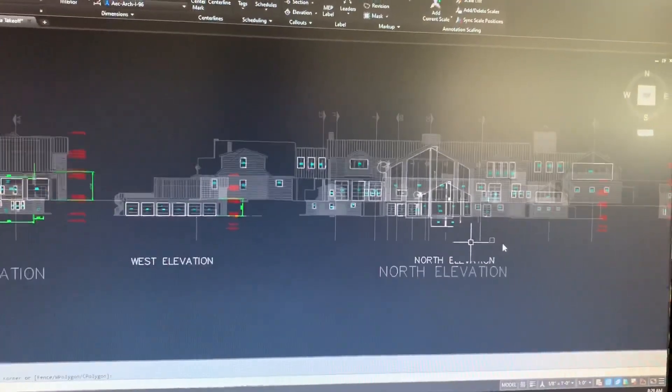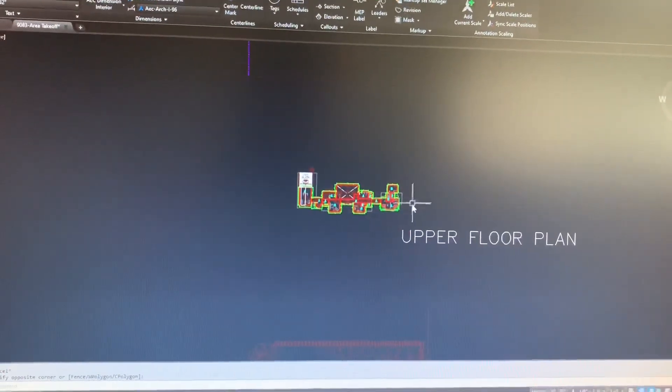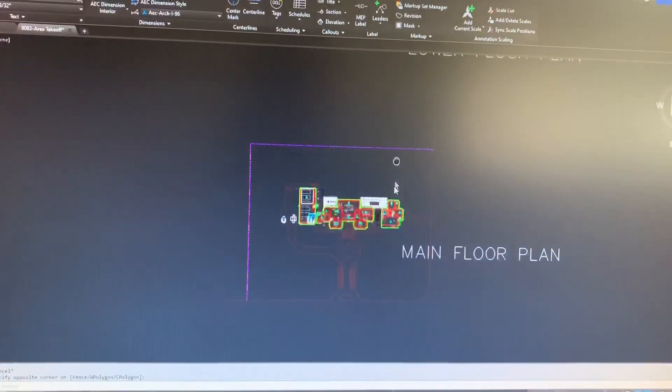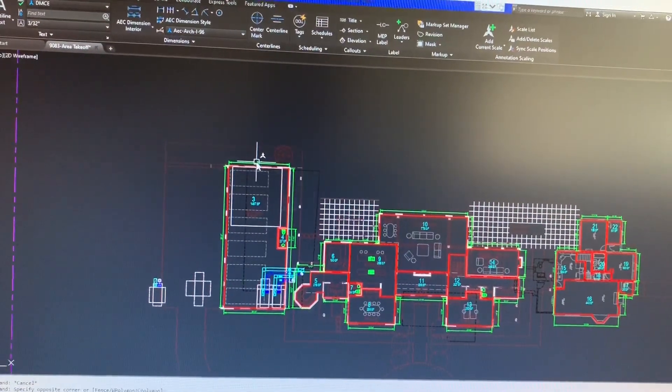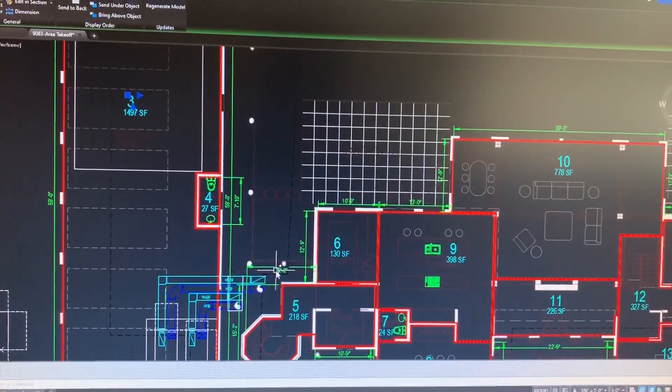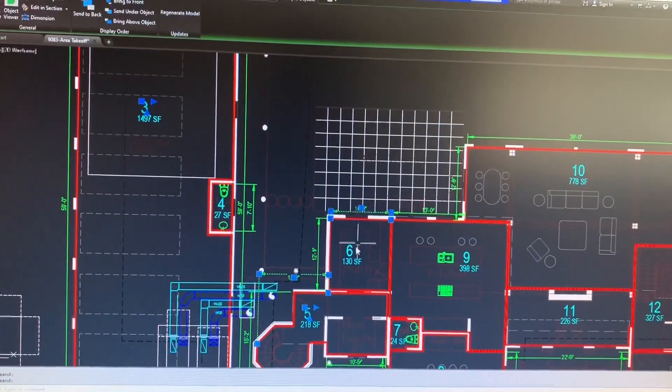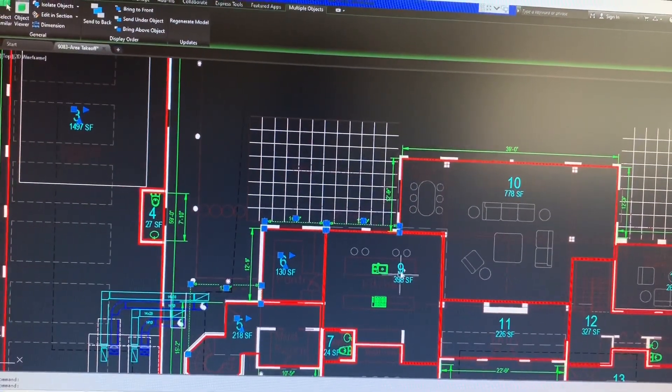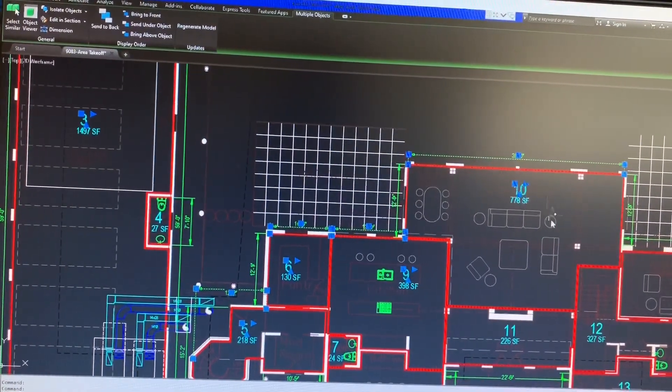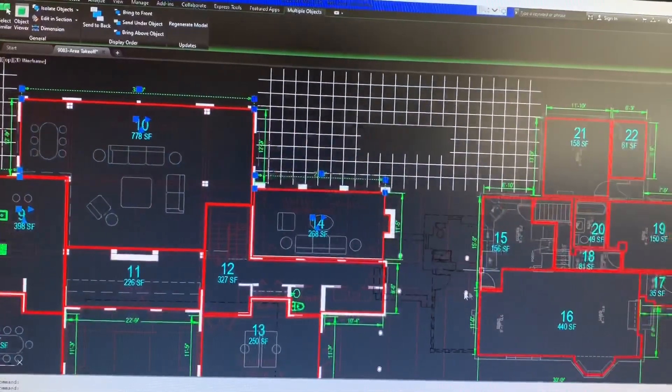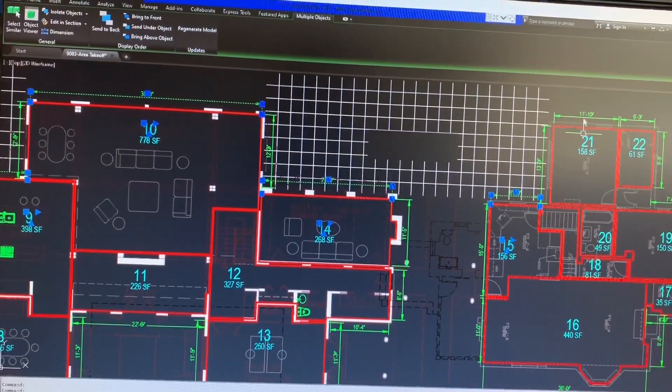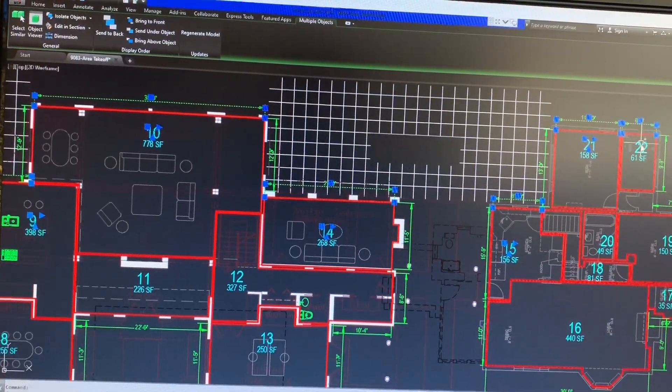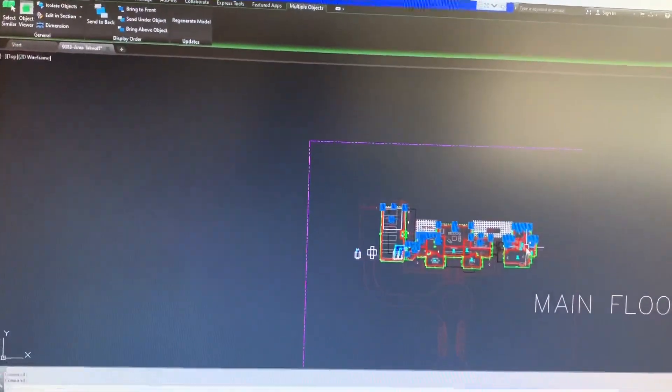Now I've got to do it for the north elevation. So what I do, I take my area takeoff plans and I just grab the perimeter. You just got to think about it, you're looking at it in two dimensions. So I'm grabbing all the zones from the north elevation. Zone 5 gets the 10 foot, Zone 6 gets the 10 foot, 13 feet goes to zone 9, 39 goes to zone 10, 23 goes to zone 14. There's a bridge here so there's no exterior elevation. You got all those.